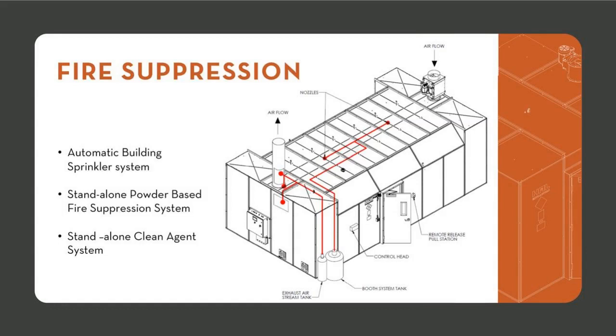The most common alternative to that would be a standalone powder-based system. A lot of our customers use a nitrogen-based powder. And so this is a standalone option. You have tanks on the side of the room, and then you have some nozzles in the room, and they're heat activated, the links snap, and then you get a release of that suppressant. There are specific places that you'll need to have sprinkler heads, but for most companies, you're going to get plans where they have already laid out where they want those sprinklers as part of that full design packet.